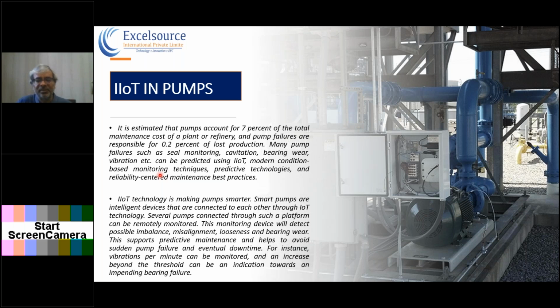So we take a call based on the temperature sensors installed at the bearing locations on the pump side and on the drive side; both sides we take into consideration. The vibration monitoring system will help us see whether the pump is properly aligned or not. If not aligned, then we need to take immediate action to stop the system before it comes to a breakdown, and align it, and so avoid a complete breakdown in the plant, which can end up losing the profit of the company.